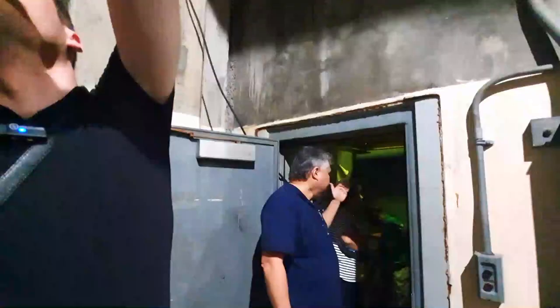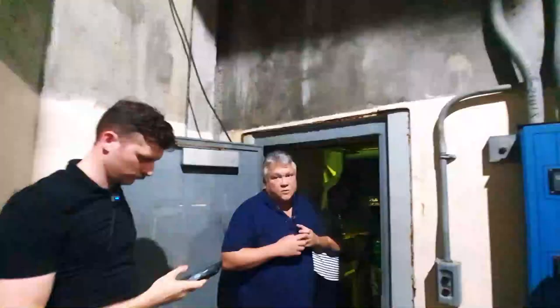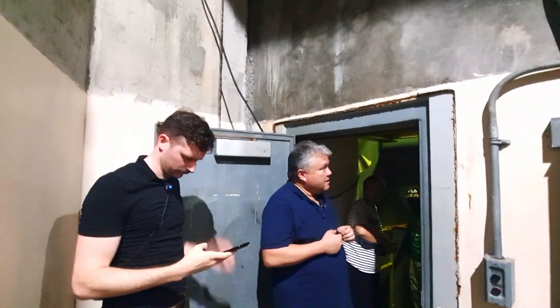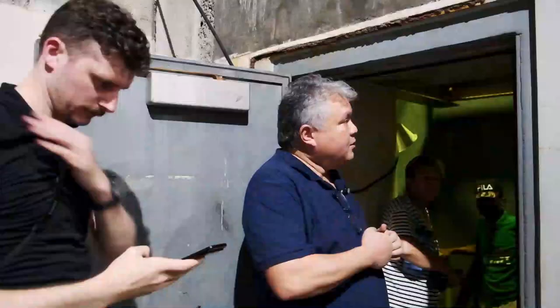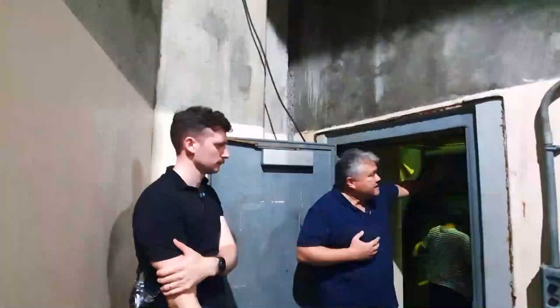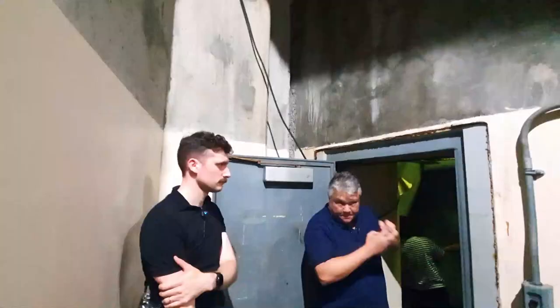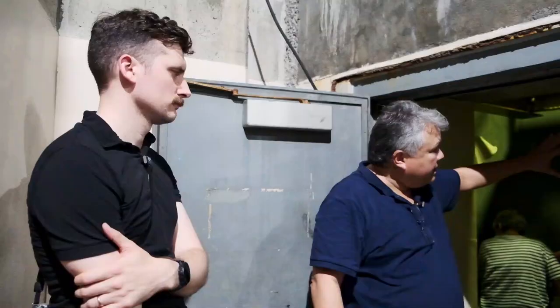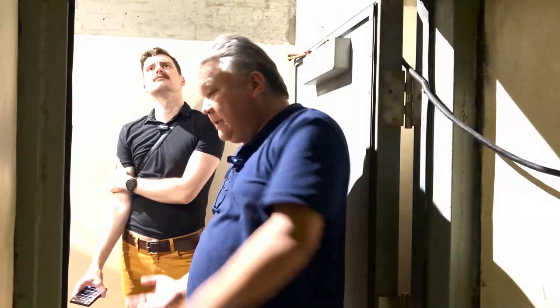There's a steel liner in there that's 1 inch thick. In between, there's an annular space connected to a filter system, which sucks air, so this is always under a vacuum. Things can leak in, but they can't leak out because of the vacuum. The pump that draws the vacuum passes through a filter system before being ejected, so if there's any radioactive material, it will be filtered before the air is evacuated. Nothing can leak out, it can only leak in.